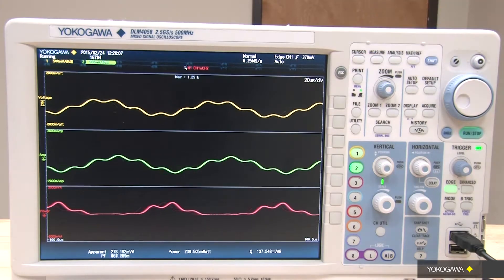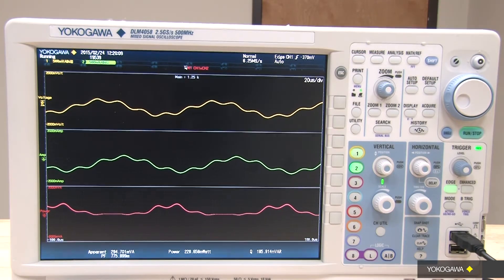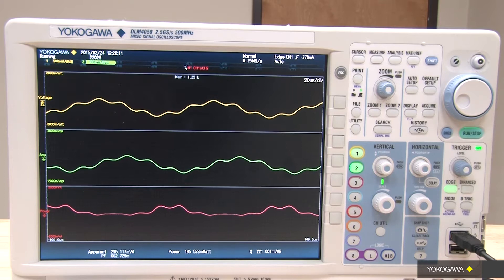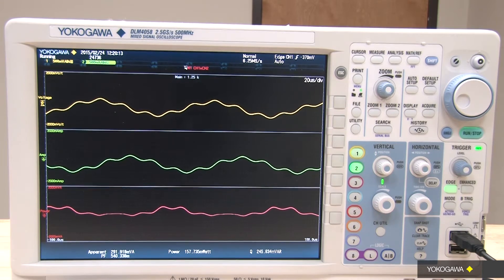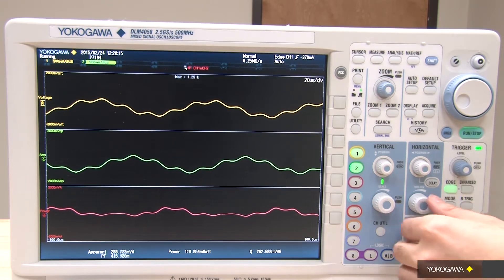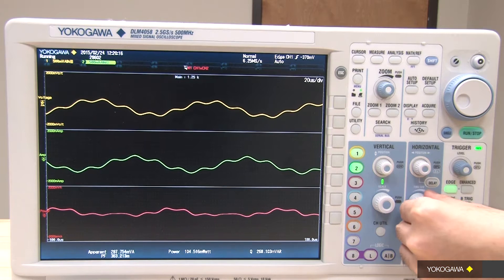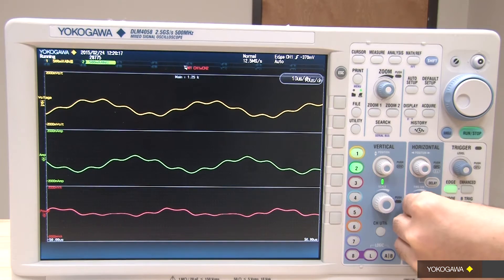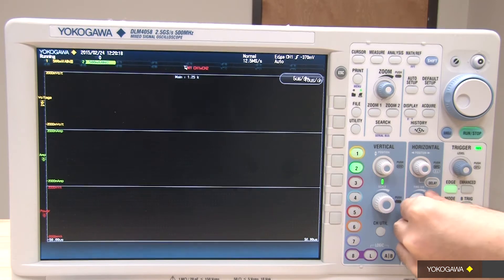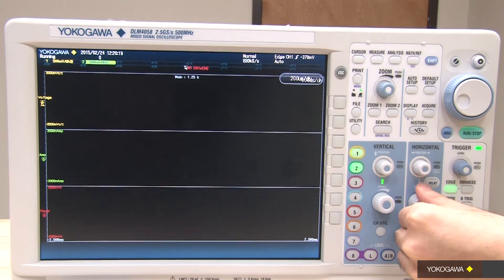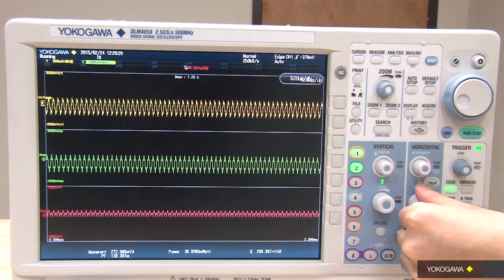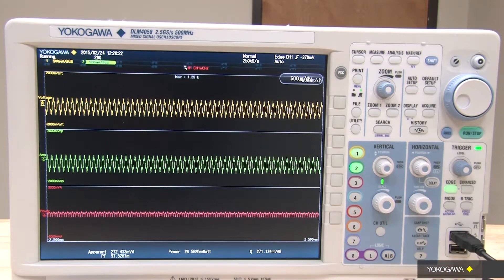Once you have set the probe attenuation, it is important to make sure you have captured enough cycles for the power harmonics to be calculated accurately. Increase the time per division until you have a minimum of ten cycles.